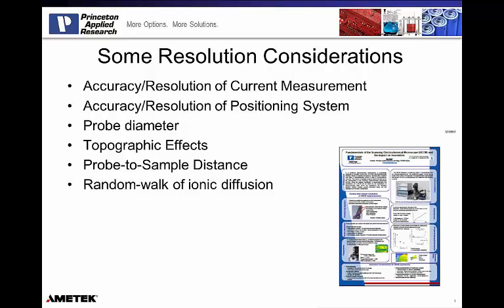First, we're going to have both the accuracy and the resolution of the current measurement. So this is done by the potentiostat. So not only what currents can the potentiostat resolve, but for quantitative work, we need to know how accurately it can measure these low currents. Then there's the accuracy and resolution of the positioning system. Again, it's how well can I report back and how well can I position the probe in a known position, and once it moves away from that position, how well can I control it when it comes back. So knowing the resolution and accuracy and repeatability of a positioning system is a key parameter in the ability of an SECM system to make the measurement.